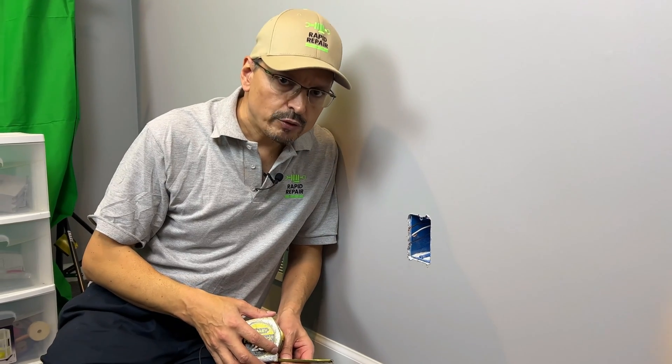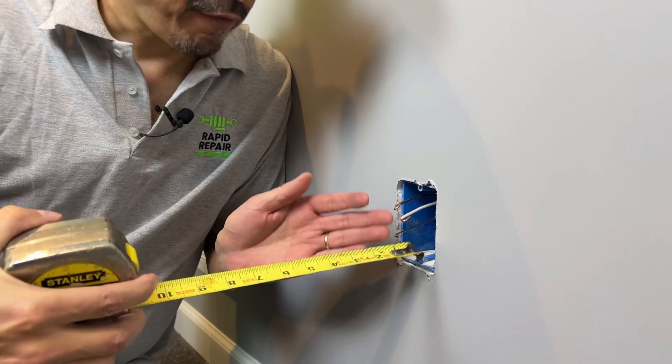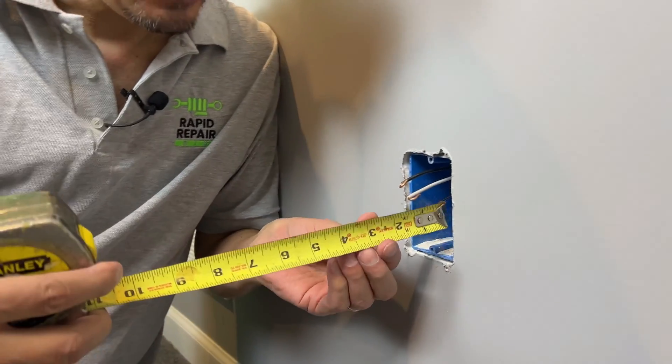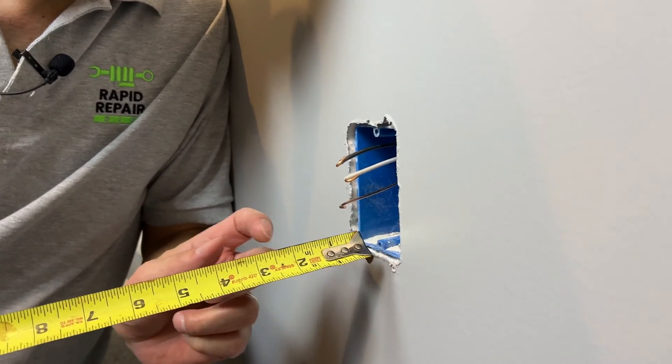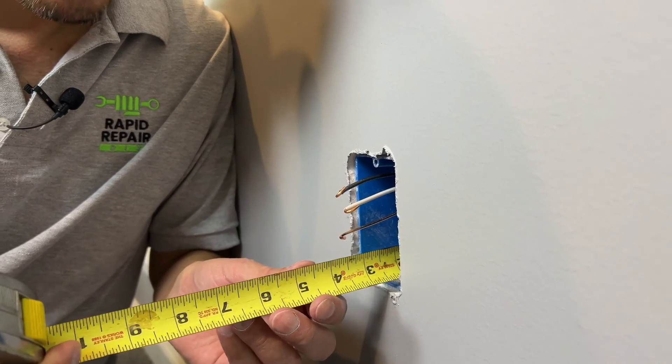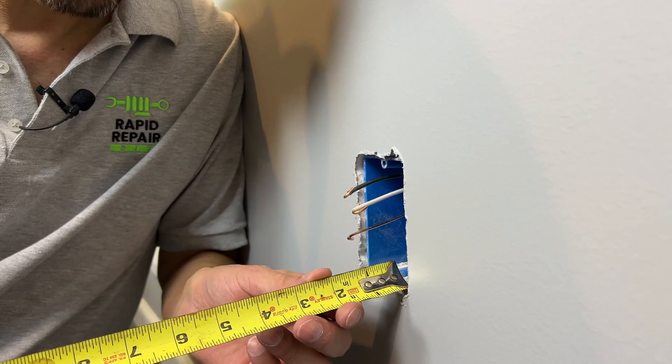The National Electrical Code states that you should have six inches of wire from the back of the box to the front and a minimum of three inches. Hope you can see that from the front to the inside of the room.